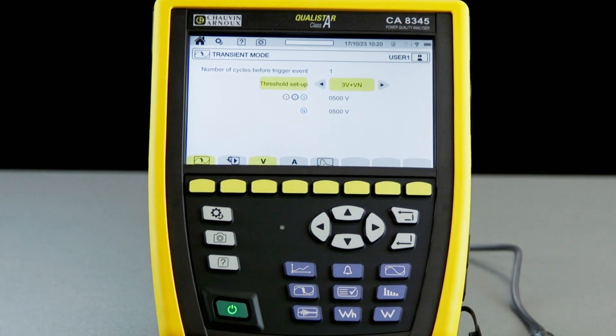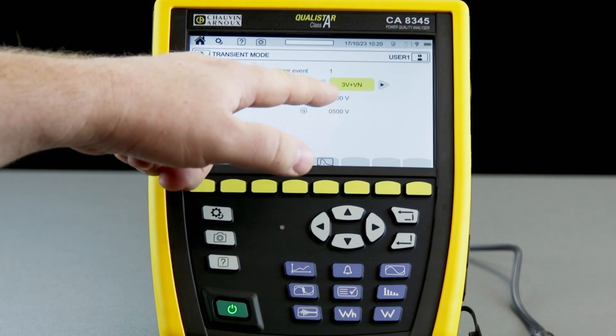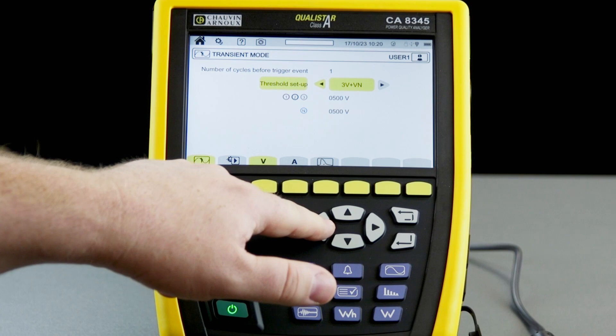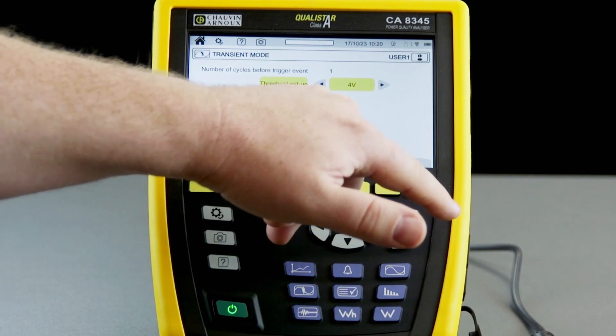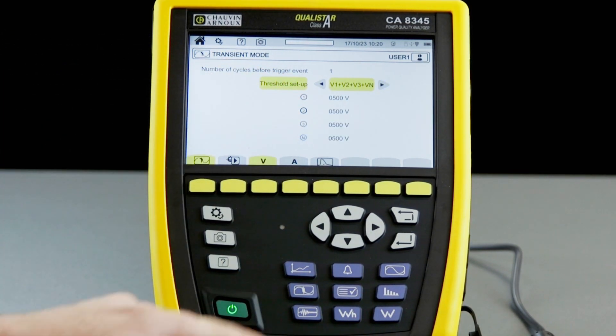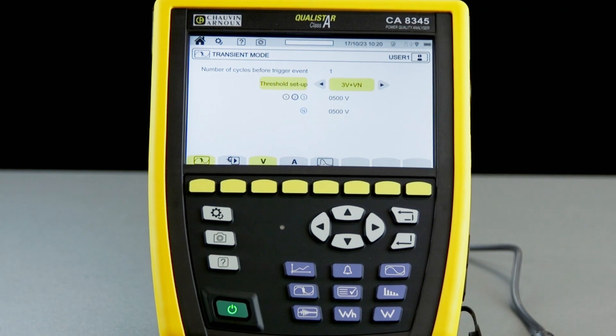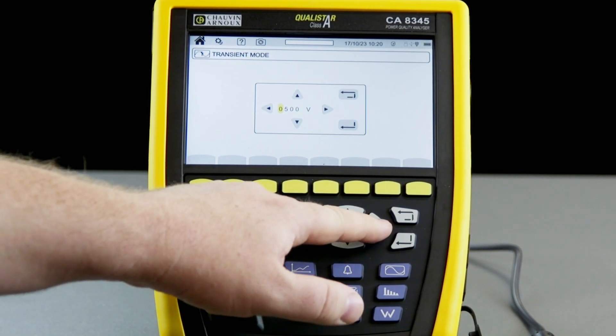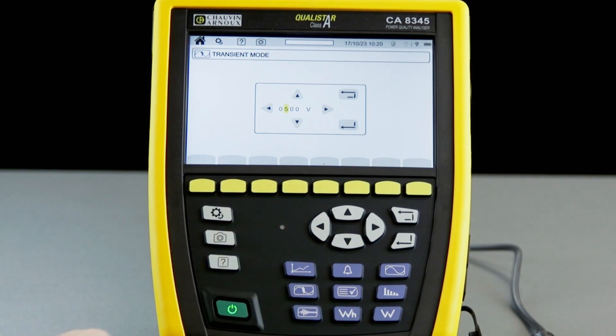The first option we have is the number of cycles before it triggers the event, which is currently set to one. We can then set the individual voltage thresholds that will trigger the transient capture. We can monitor voltages using one threshold for all, separate thresholds for each, or different thresholds for the line conductors and the neutral. In this case I'll select one threshold for all, and configure it using the arrow buttons to set the desired voltage.